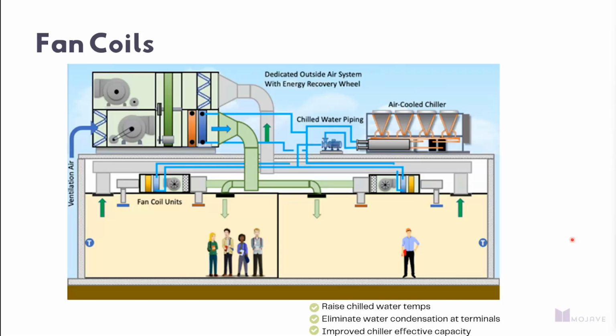And as a byproduct of that, you actually get to raise your chilled water temp on your chilled water loop. And when you do that, you see a better kW per ton out of your chiller, as well as a higher effective capacity out of that chiller. So you have the ability to maybe get, rather than 80 tons out of a chiller for original design, you're able to get 90 tons or 95 tons out of that chiller by running a 50-60 delta out of it rather than a 42-52 as an example. A little less front of mind example of how a product like this can pair with a chilled water system to deliver a high performance building.